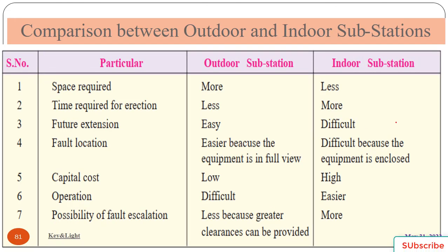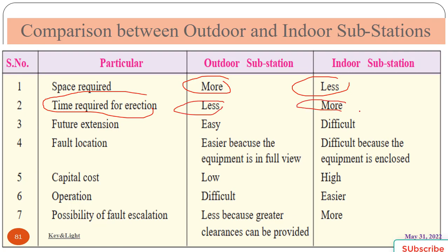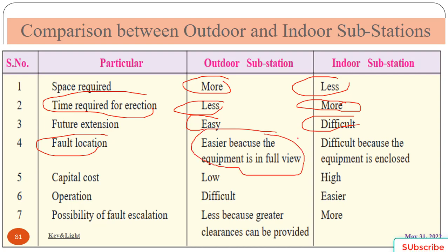And this is a comparison between outdoor and indoor substations, compared with particular characteristics. One, space required: in outdoor it is more, and in indoor it is less. Time required for erection: it is less in outdoor and more in indoor. Future extension: it is easy in outdoor and difficult in indoor. Fault detection is easier in outdoor because the equipment is fully in view, and difficult in indoor because the equipment is enclosed.